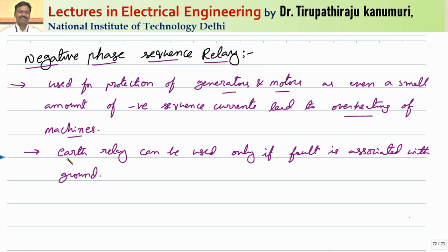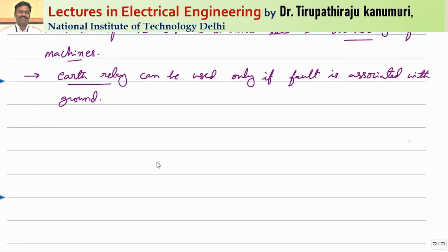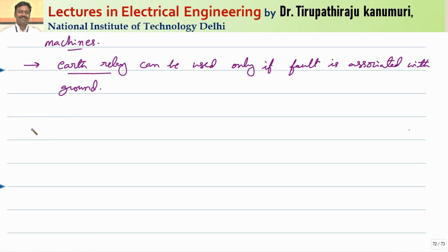We have already discussed the earth fault relay. Whichever faults are related to earth, it will detect. But the problem is if the fault is not connected to the earth, or if there is unbalanced loading on your machine, these relays cannot operate even for small values of unbalance. If the loading is less than the rated load and there is a small unbalance, this earth fault relay or overcurrent relay cannot detect those negative sequence components. To avoid this problem, we go for a bridge type circuit — there are two types of circuits available.